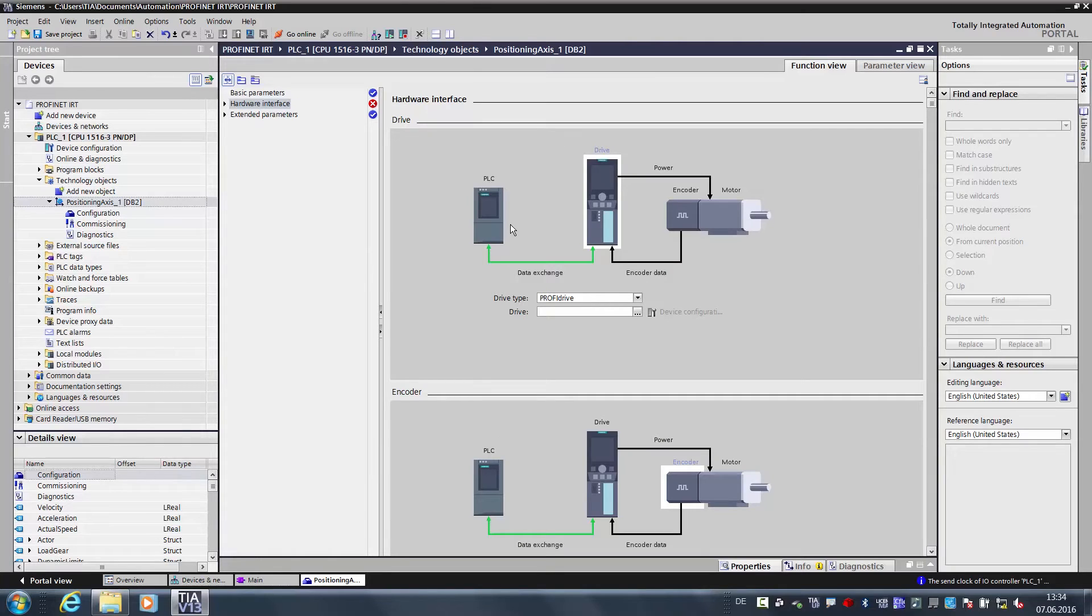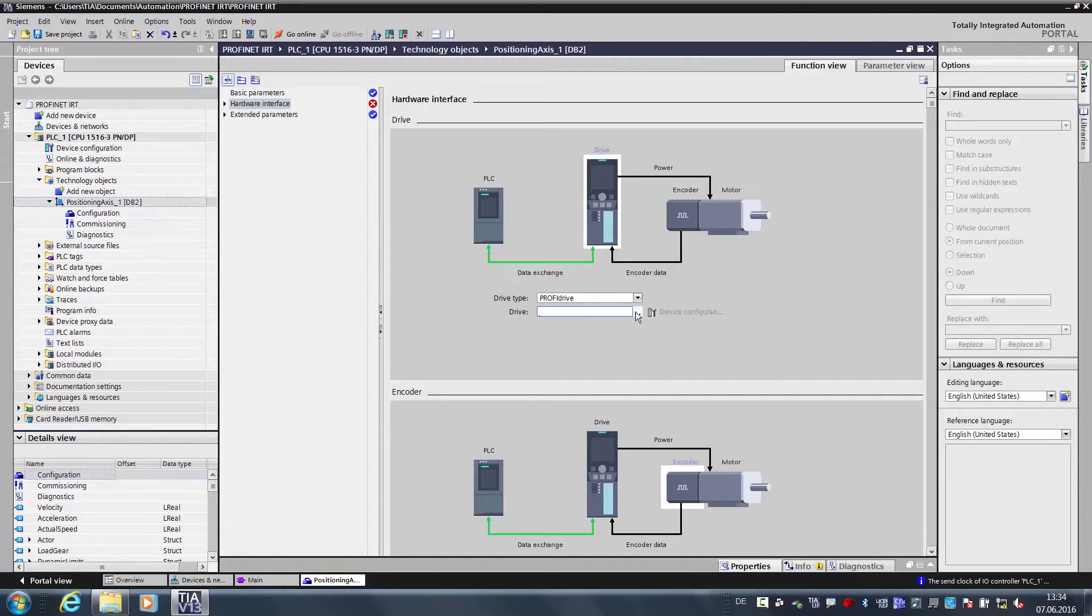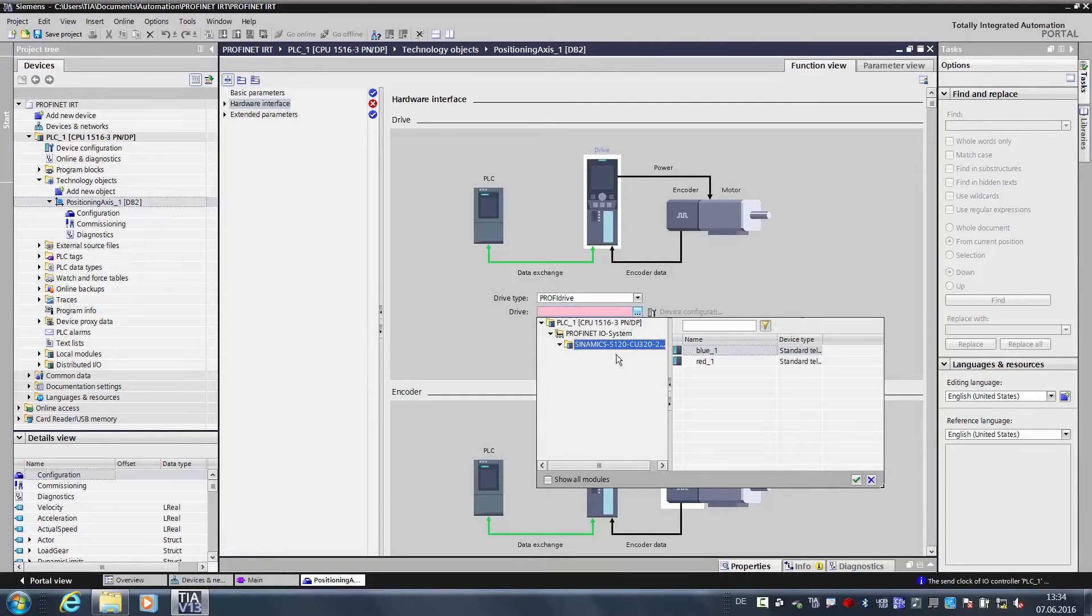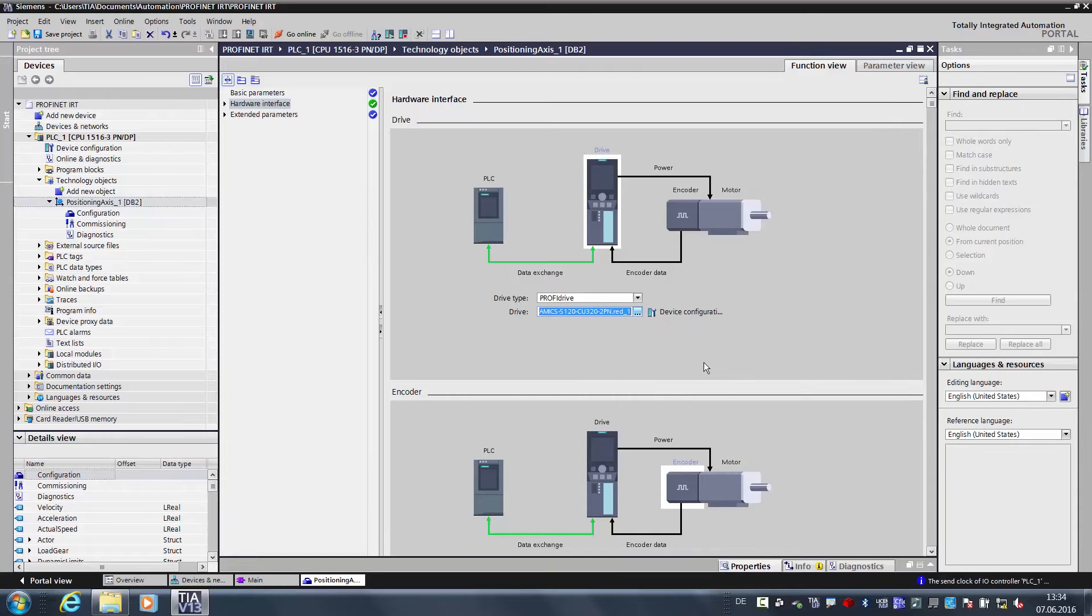Now we define the hardware interface. The drive is now preset to PROFIDRIVE. PROFIDRIVE is a standardized interface between the drive and the controller. The drive and the controller speak the same language, and when you replace the drive and install a different drive with a PROFIDRIVE telegram, the controller and drive will continue to understand each other. Here we now select the drive that we have integrated into the hardware configuration. The red axis, in other words the upper axis on our test box, will later be the master axis, and that is why we select this red axis here.